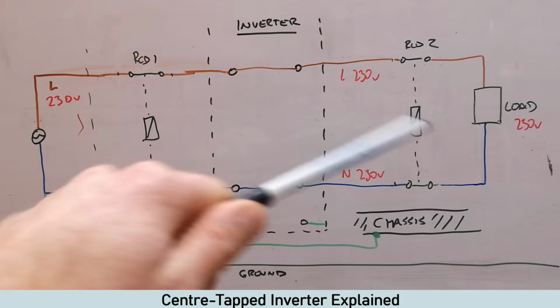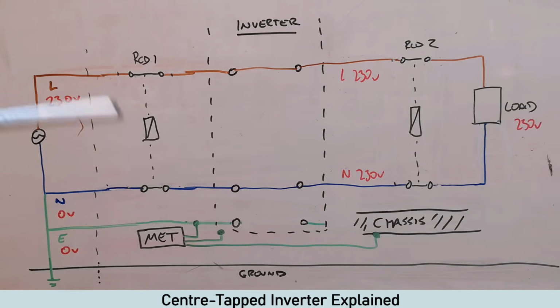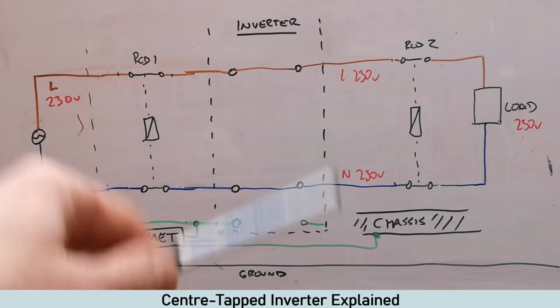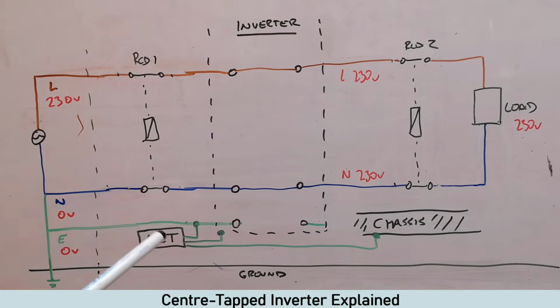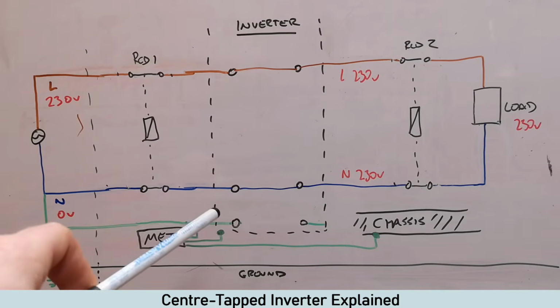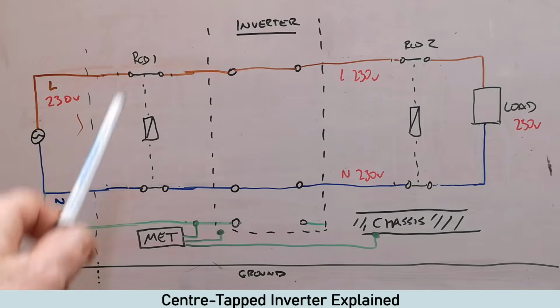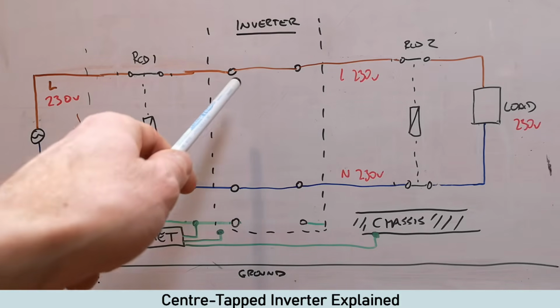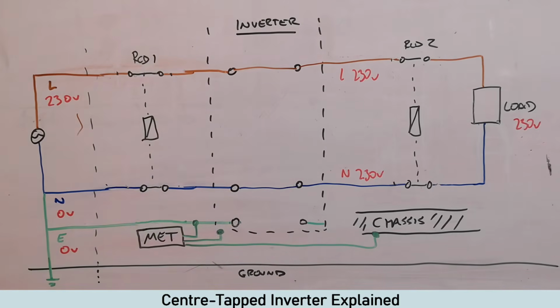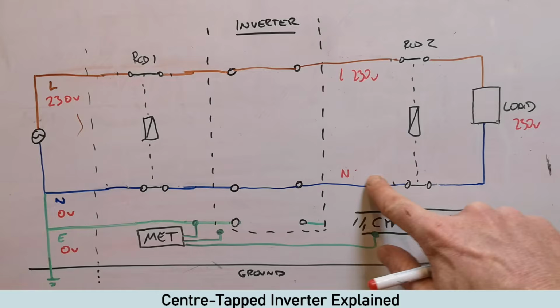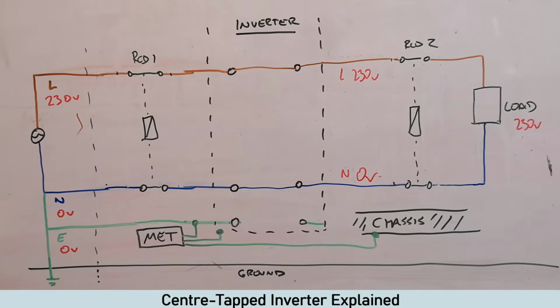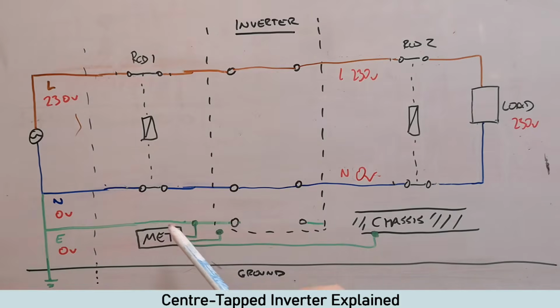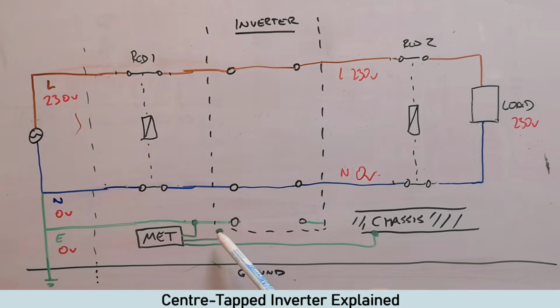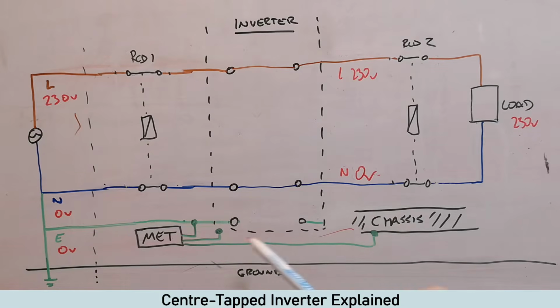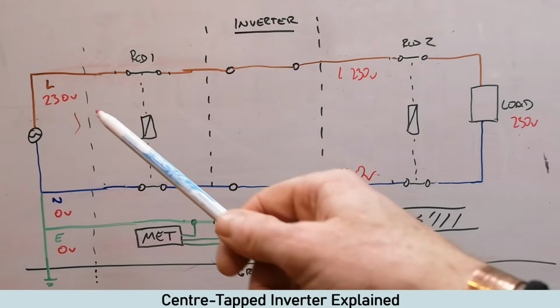So I'll just briefly explain what's going on with these RCDs. Now, this is very brief. I'll be honest, RCDs and earthing and inverters need whole videos of their own. So this is just a brief overview, okay? What we've got here is the hookup is on. So 230 volts coming in. This is your bypass switch in your inverter. It's coming through and we have 230 volts and 0 volts. Happy days. And then what I've also done, I've put the earth terminal, so everything's linked. That's the casing of the inverter charger, the chassis, and all the other earths connected to it. I've not included everything because I haven't got space. So basically this is a happy system.